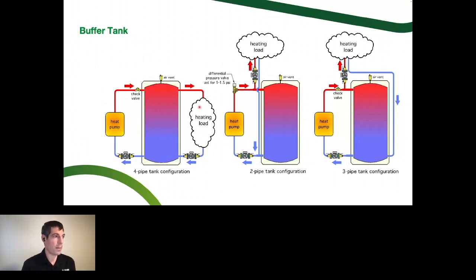So let's say the delta T on the heat pump side is 20 degrees, and on the load side, it's 5 degrees. For whatever reason, we've got kind of a big difference there. In that case, we're going to have this pump moving a lot faster on the right side, and it's going to churn up the stratification of our tank. So that's a little bit of a problem because ideally we stratify this buffer tank so the hottest water is at the top. We don't have to recycle it as frequently. If we're moving really fast through this tank, we're going to churn it up.